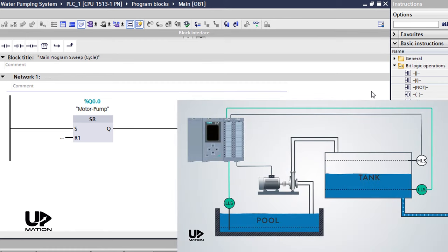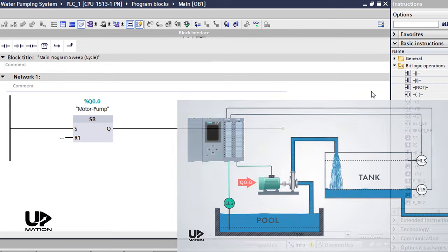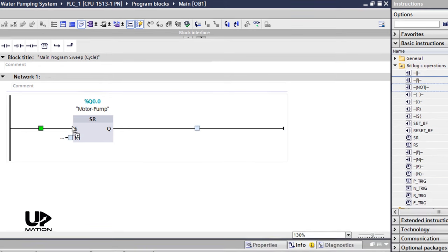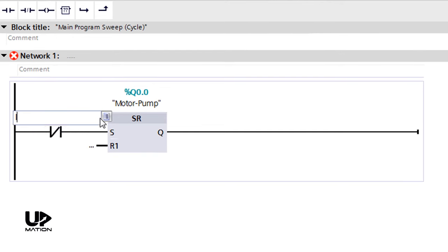The only condition required for starting the pump is losing the I0.1, that is the tank's low-level switch. So I connect a close contact to the set input of the flip-flop and will type I0.1 here and press Enter. This way, when the I0.1 is false, then the set input of the flip-flop would be 1 or true, and consequently the pump will turn on.